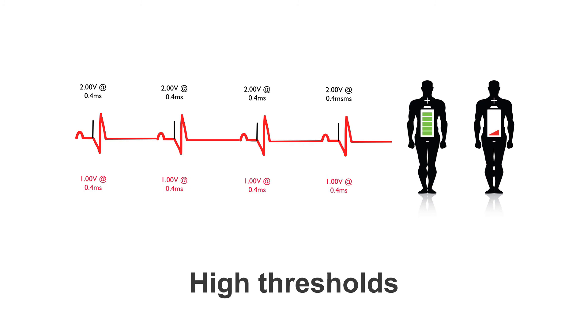Quite often by making that small change, we can go back and look at our values again. In this patient, their threshold has returned to a nice 1 volt at 0.4 milliseconds. This enables us to put the output pulse at 2 volts at 0.4 milliseconds, and still maintain safe function of the pacemaker without the additional drain on the battery. 2 volts at 0.4 milliseconds is a very normal output pulse for a pacemaker, so this person will have good longevity from their device.